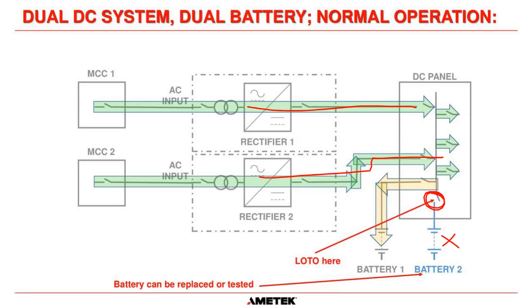Somebody just asked, they've never heard of LOTO before. It's lockout, tagout. In other words, it's a way of confirming isolation of a breaker. It's putting a lock on it and a tag to say who put that isolation point on, and that can only be removed by the person who put the isolation on in the first place. It is for electrical safety.